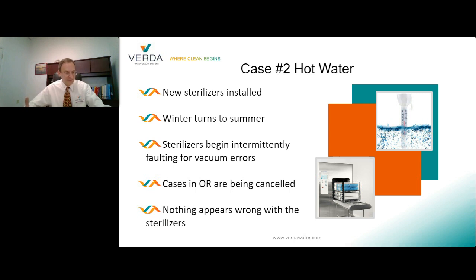Now the sterilizer's vacuum pumps were designed to be cooled with water no hotter than 68 degrees Fahrenheit. And they continued to perform as the water temperature rose and went above 70, and then above 75. But when the river's water temperature got to 85 degrees, the vacuum pumps started to fail. Now, replacing the failed vacuum pumps helped temporarily fix the problem, right?